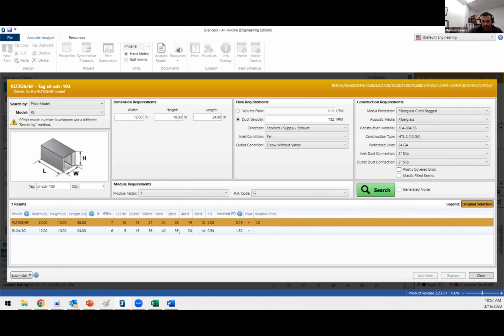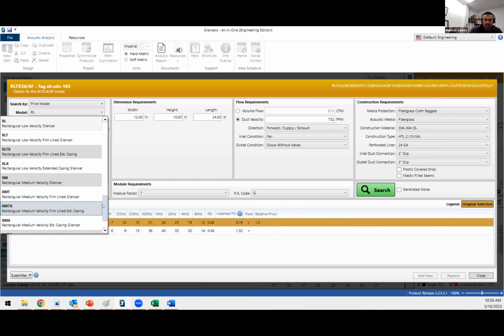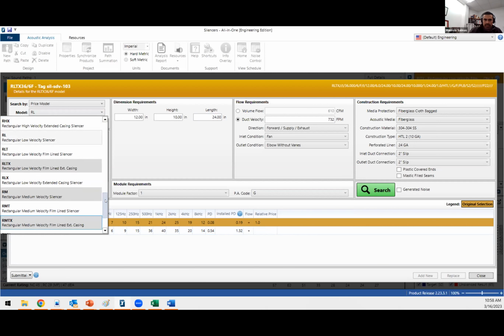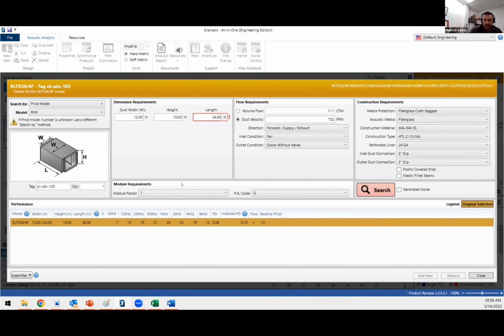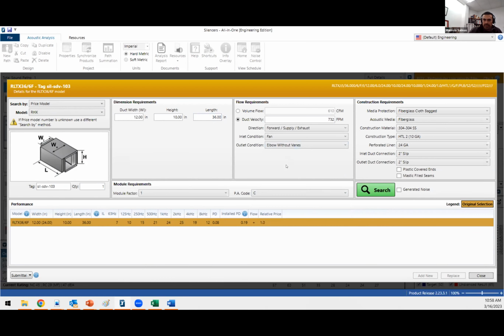And it actually gave me 10 more points on the 2,000 hertz. So if you want to start gaining more performance after that, you'll see that it really increases your pressure drop. You see that? Just a little. The best way to do that is to use a high-speed silencer, which tapers the internals, which allows you to do some static regain. And remember, the limit is 36, and make it longer. Making the silencer longer will allow you to get that performance that you need.